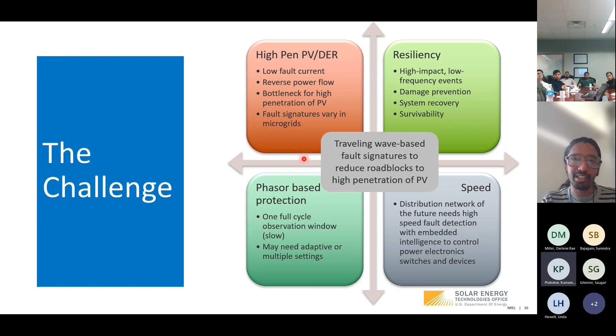So we proposed traveling wave based protection, or fault signatures, to detect and locate faults, because traveling waves are very fast—they travel close to the speed of light. If you can capture that, you're able to detect and locate faults without depending on fault current contribution, avoiding all the challenges that come with it.